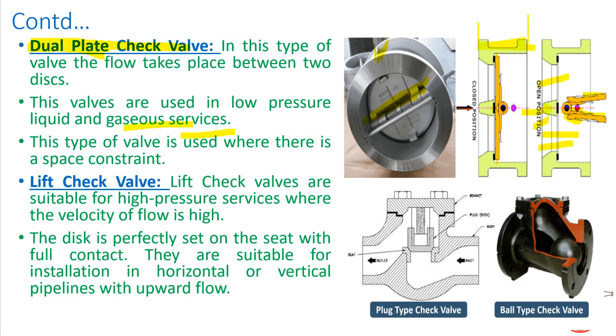Lift check valves are considered for steam, high-pressure, or high-velocity lines. There are two types: plug type and ball type. The fluid enters and lifts the plug vertically upward to allow flow. If a ball is used instead of a plug, it is called a ball type lift check valve. The disc is perfectly seated on the seat with full contact. They are suitable for installation in horizontal or vertical pipelines with upward flow.